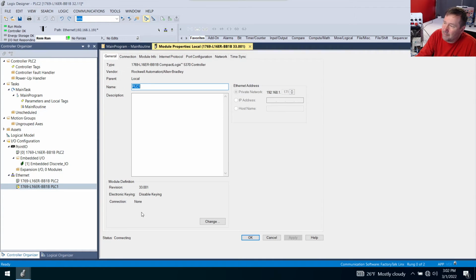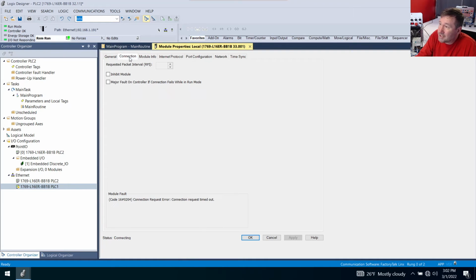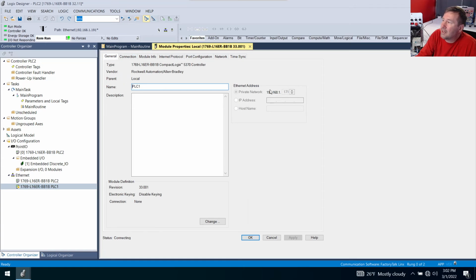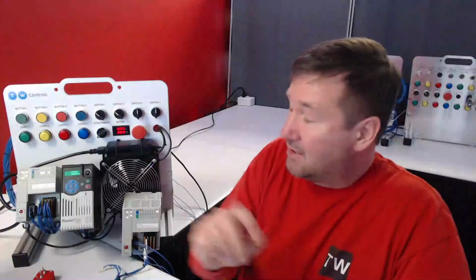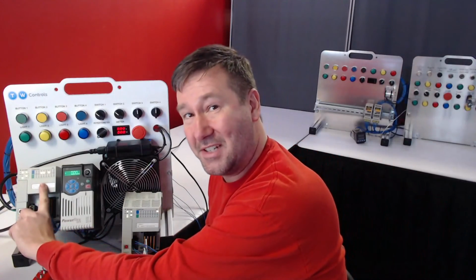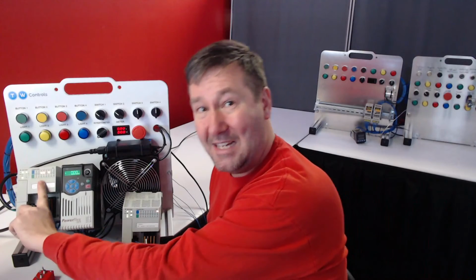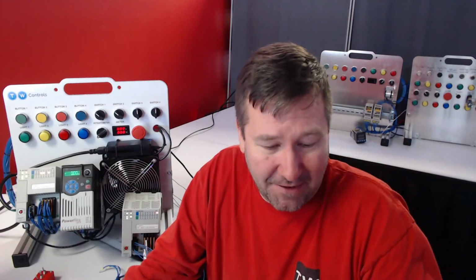And here's one time I just can't stress enough: you need to put blinders on to everything that's on here. We have a connection issue. We need to go to the Connection tab. And right here it says Connection Request Error, Connection Request Timed Out. So if I go back to my General tab, I have the IP address 192.168.1.171. But I told you this one is 192.168.1.181. So I typed the wrong IP address in.